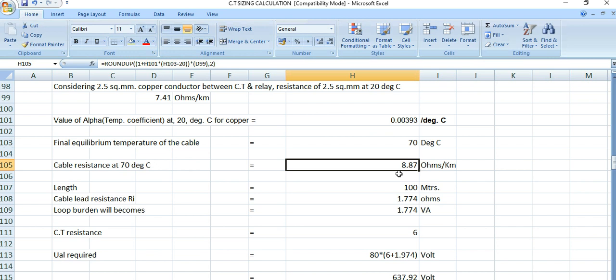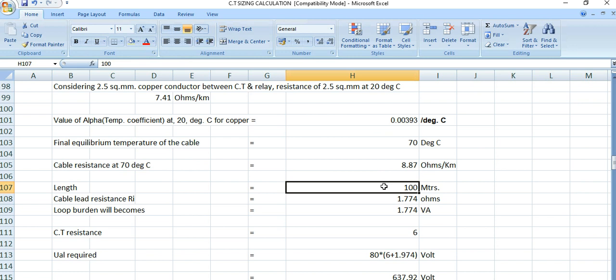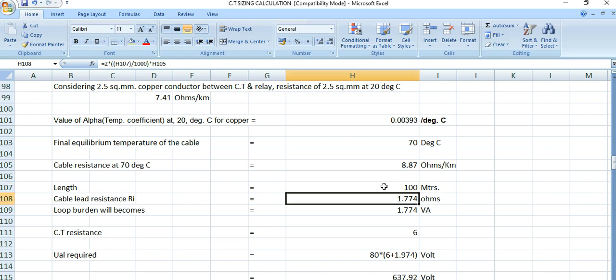The length is considered 100 meters. In the previous examples for protection CT or metering CT, we considered only 10 meters because that was nearby at the same location. But here the length is 100 meters because for differential protection we need to consider two CTs — one upstream and one downstream at two different locations — so this length will be higher compared to protection or metering CT.